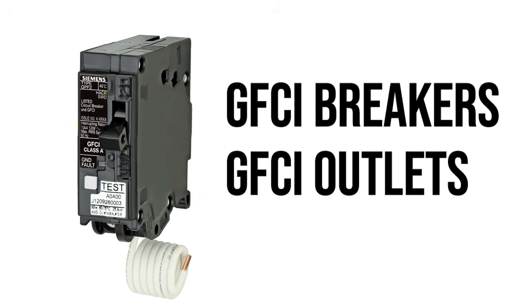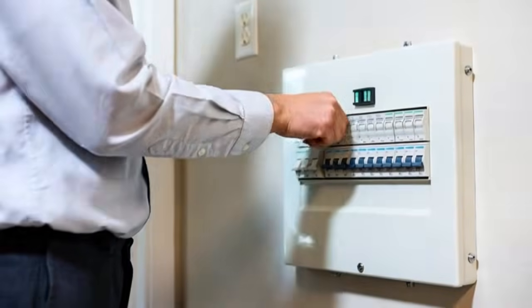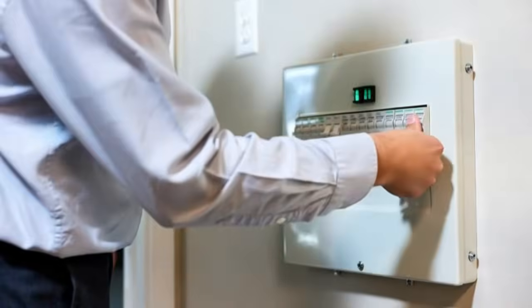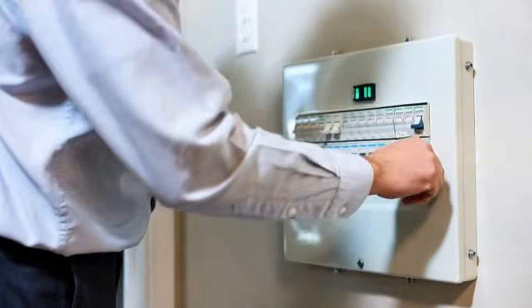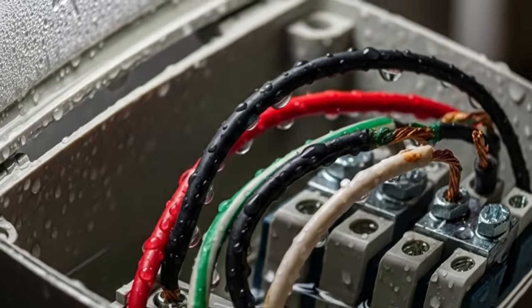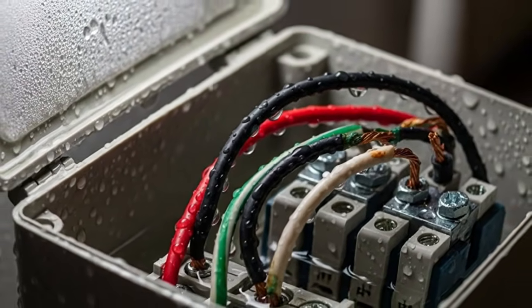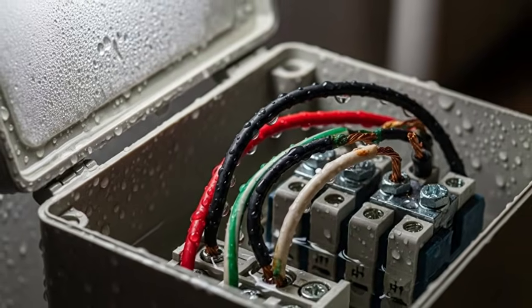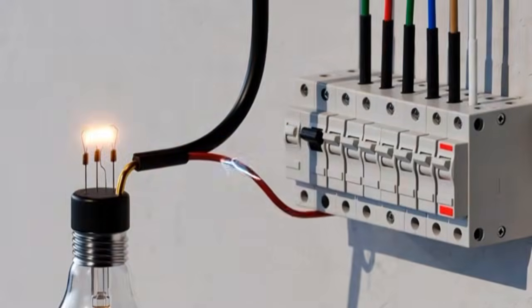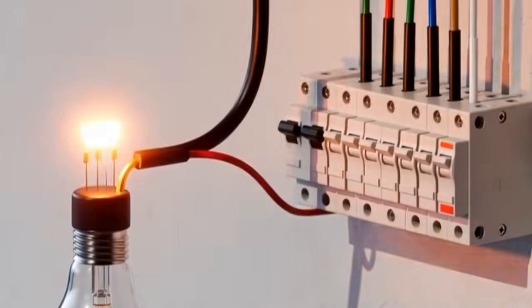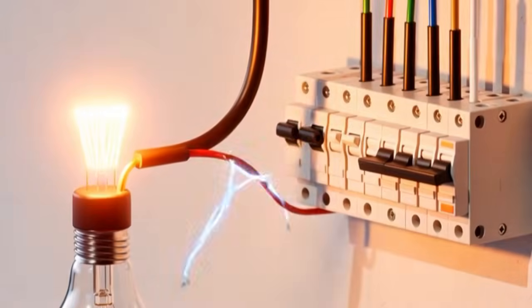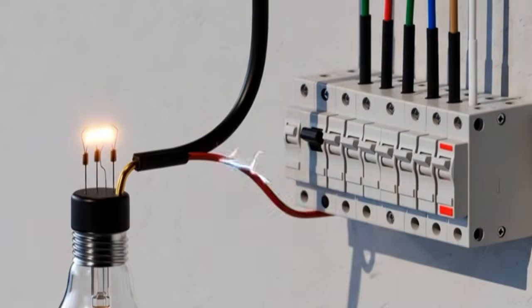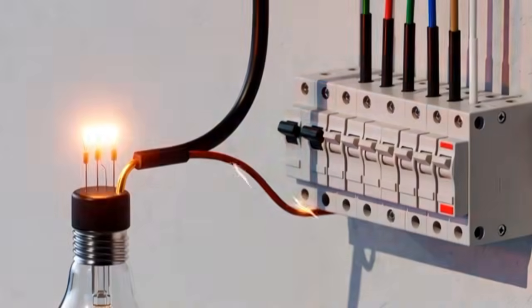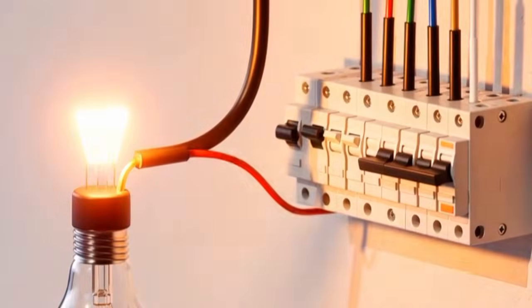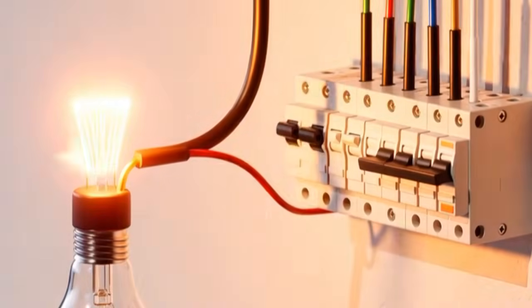A ground fault can prevent a breaker from resetting because the fault path remains active. Moisture inside a junction box, a damaged appliance cord, or a failed appliance can all maintain the ground fault condition even when you think everything is unplugged. If your breaker serves a kitchen, bathroom, or any wet location and refuses to reset, a ground fault should be high on your suspect list.